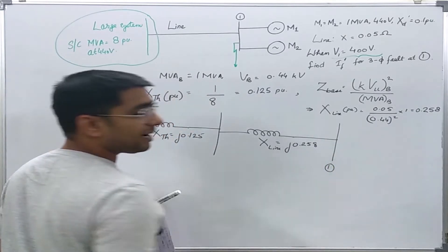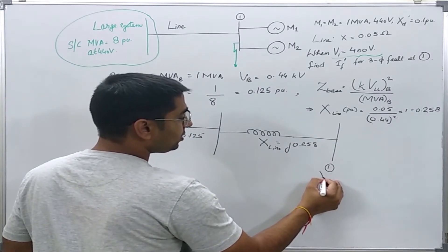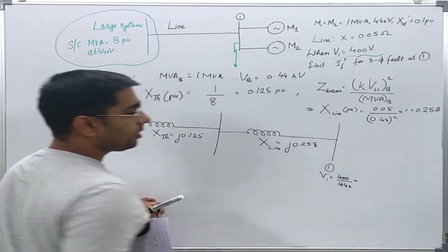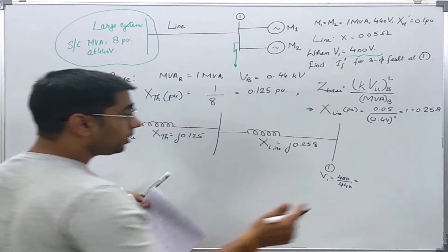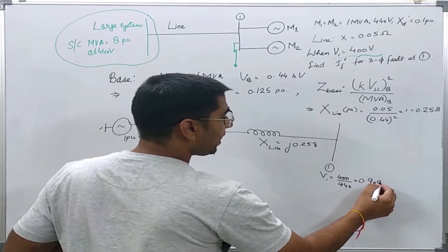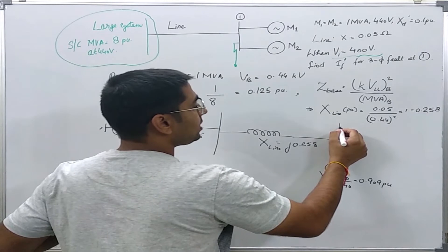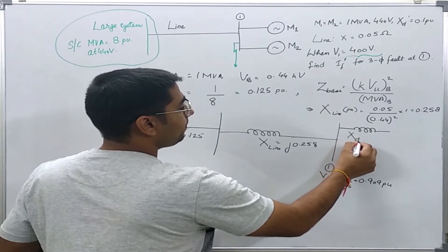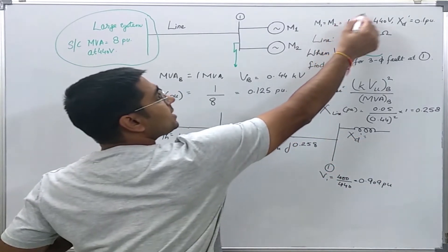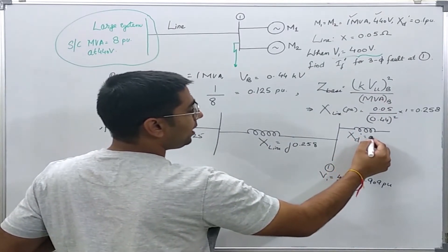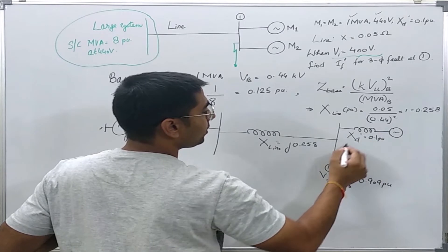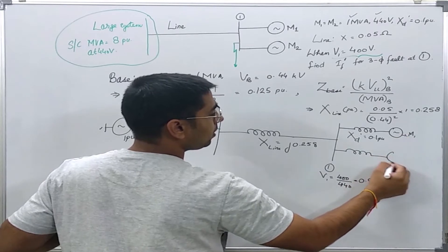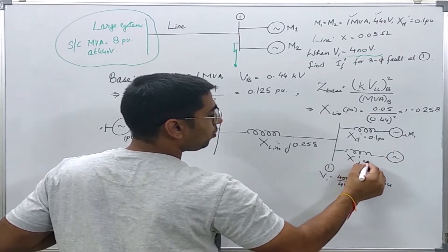Bus 1 has a voltage V1 of 400 volts, which in per unit is 400 divided by 440, equal to 0.909 per unit. The two motors each have XD' equal to 0.1 per unit, since base voltage and base MVA are the same as the machine ratings.